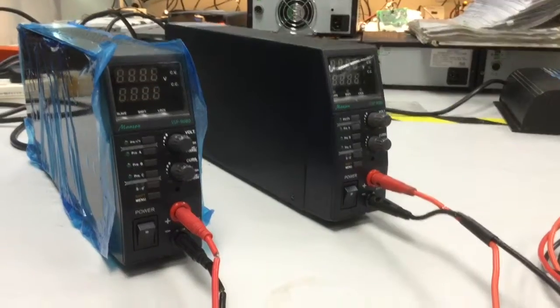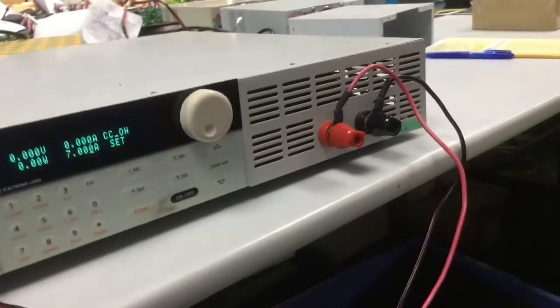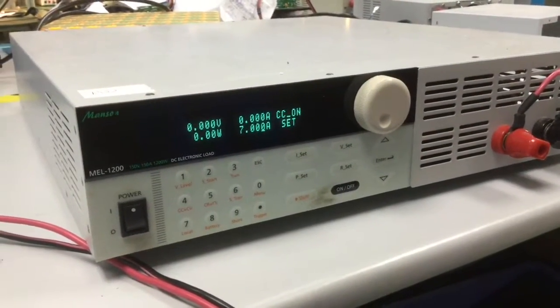Now, we have the actual setup with two equal-length cables drawn together at this end, and then finally, turn up to an electronic load, we set the electronic load to 7A.